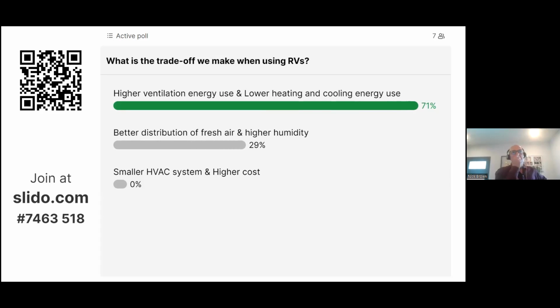You know, I'm like you, my guards go up, my alarms go off when someone's trying to sell me something with no drawbacks. So it's good for us to go in eyes open with the fact, hey, we're going to spend more money to better ventilate this building, higher ventilation energy usage, but we're counting on, by tempering that outside air, energy savings to offset that. But I would argue, even without those energy savings, the ability to make it balanced ventilation, filtered, better distributed, would likely justify the expense.